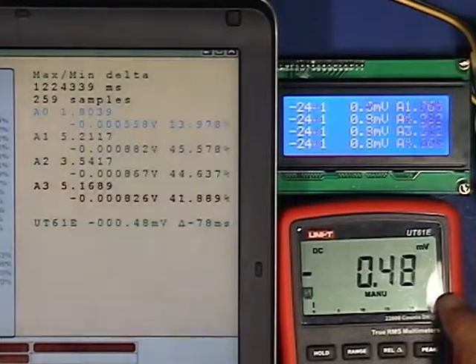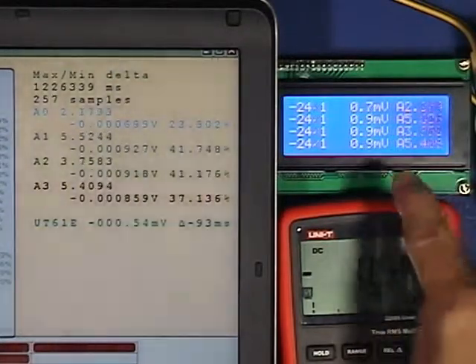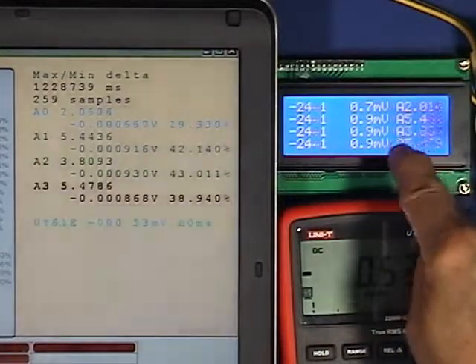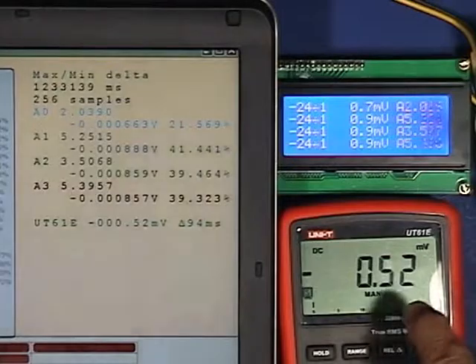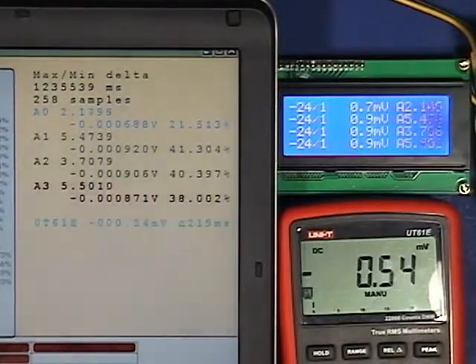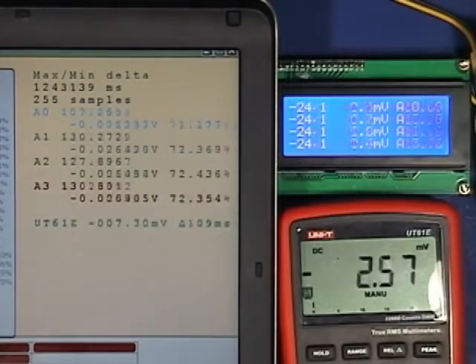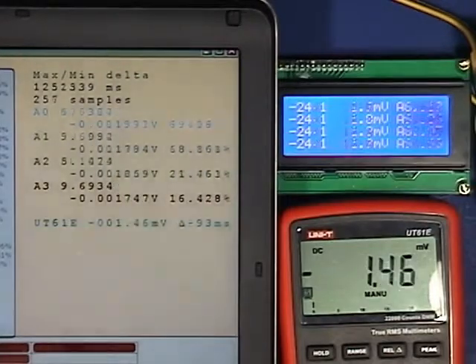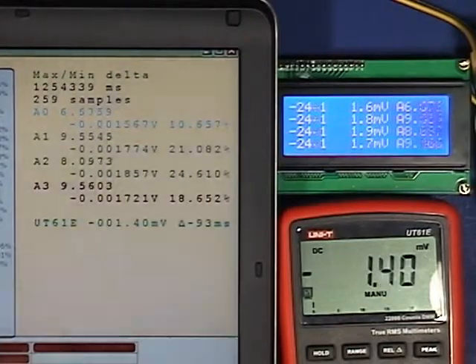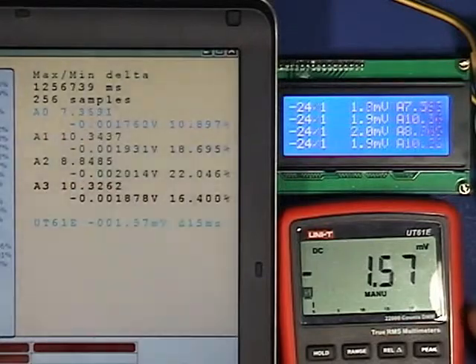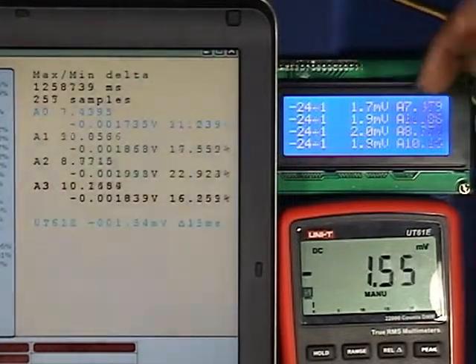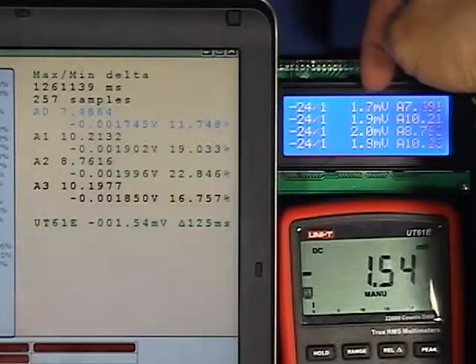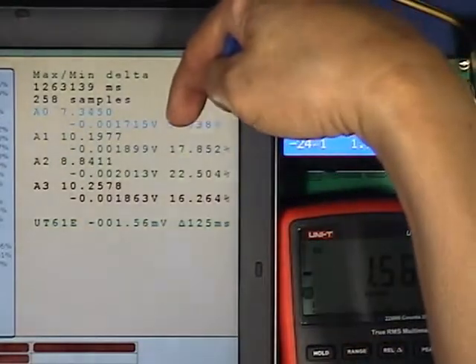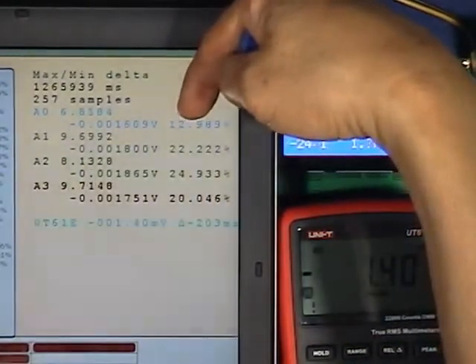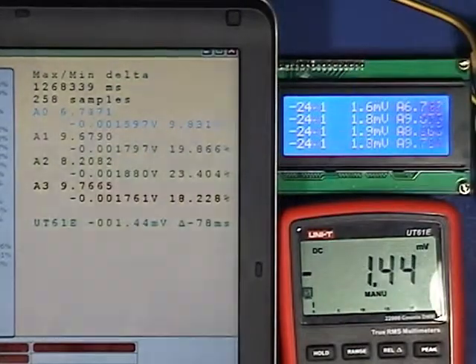At minus 0.4 millivolt, this guy is measuring minus 0.7. Not bad at all. It's 50% error, but we are less than 1 millivolt. I want to get this over with, otherwise I'll switch the trim pot. At 1.4 millivolt, this guy is giving me a very meaningful number. More than 20% error, but the number is still very meaningful once it's settled in.